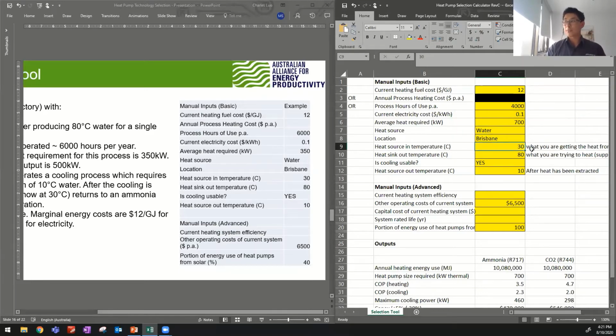The heat source and temperature. So where can we extract heat from in an aquatic center? You might be taking it from the chilled water loop for your HVAC, for example. That will come in at, say, 20 degrees, and you want the water temperature going into the pool to be about 50, let's say, to mix it with the makeup water to turn into the temperature you want. And the chilled water from the HVAC system will be about 6 degrees at its coldest. So let's ignore all this for now.